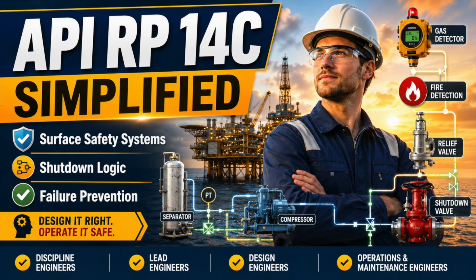Forced draft burners must prove airflow and blower operation. Low process flow through heated tubes can create rapid overheating before a remote temperature sensor responds. Startup procedures must ensure complete fuel shutoff, purge the firing chamber, limit trial for ignition time, prove the pilot, and require deliberate restart after flame failure. Many serious events begin during startup, relighting, shutdown, and return from maintenance, not during stable operation. The operating procedure is part of the safety system.